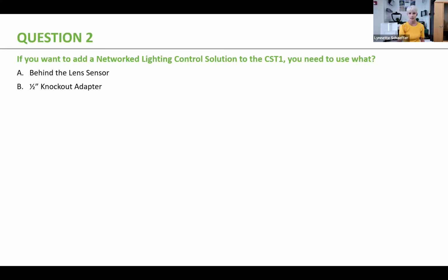Okay, I'm going to end the poll. Slightly better than last time at least. If you want to add a network lighting control solution to the CST1, you need to use a 1/2-inch knockout adapter. Remember, the behind-the-lens sensor is only a standalone microwave solution. The 1/2-inch knockout adapter gives you the ability to add network lighting controls or a PIR sensor instead. That's the key takeaway from that one.